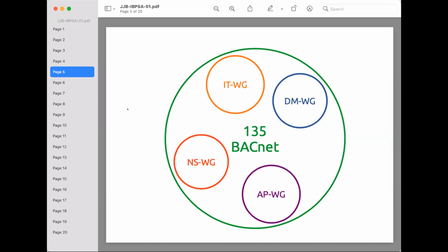So a few years after BACnet was published in 1995, there started to be a wide variety of general purpose and application specific devices, for example, a variable frequency drive controller and variable air volume terminal units. And while it's relatively simple to know what BACnet objects are defined in a device, the object name and description are just simple character strings where the content is left up to the vendor, or in some rare cases, coordinated with naming conventions created by the customer.